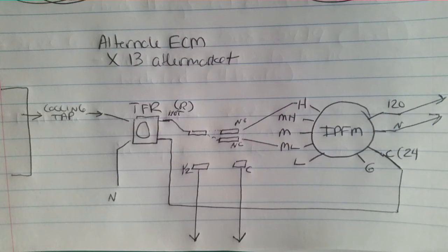On the low voltage side of the transformer, or the secondary side there on the right, we have an R hot on top, and you have the common on the bottom. And you see the common's going to go to the indoor fan motor, which is an X13. X13 will have 2 plugs. We'll have a speed plug, and we'll have plugs for the high voltage power, the ground, and the common low voltage. So we have our common running over there to that part of the indoor fan motor plug. On the left side of the indoor fan motor, we have all of our speeds. I have 5 listed. Doesn't necessarily mean there'll be 5. That's what we're using.